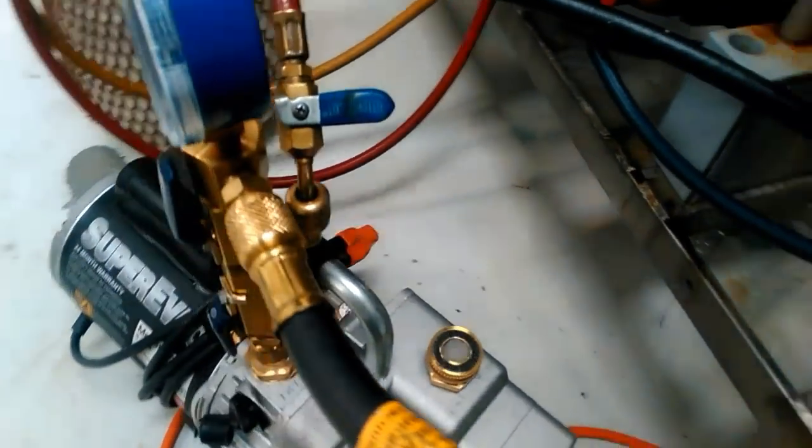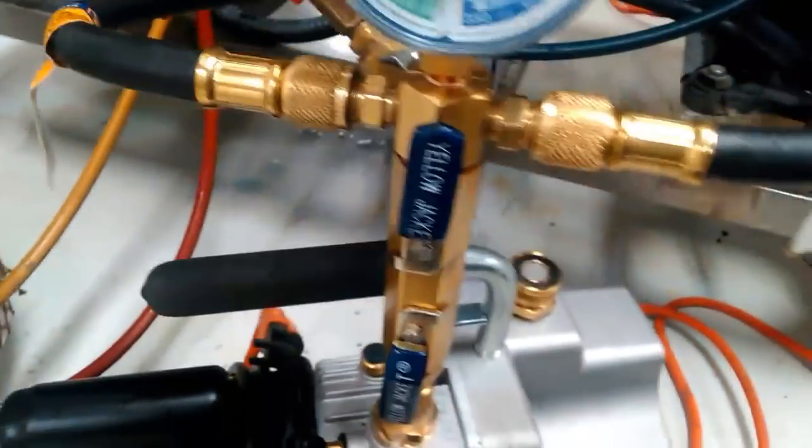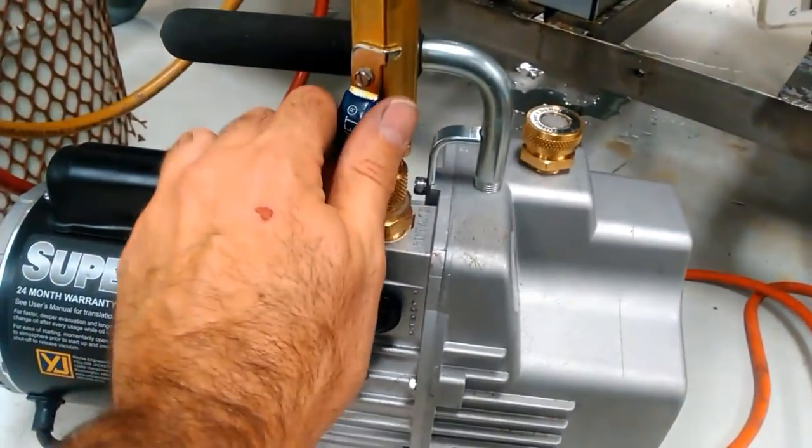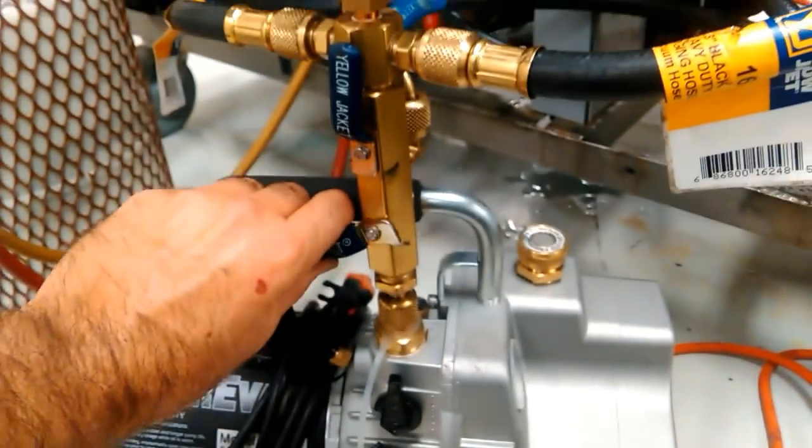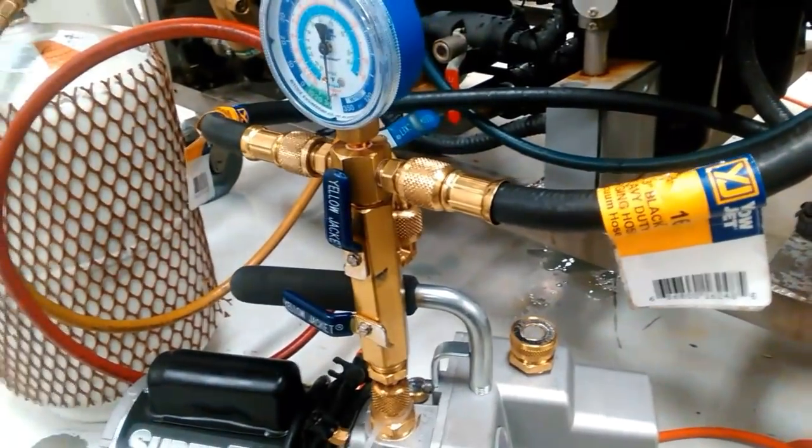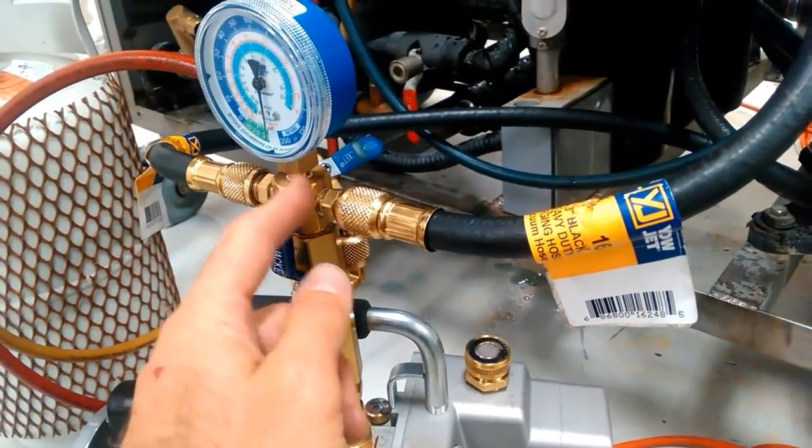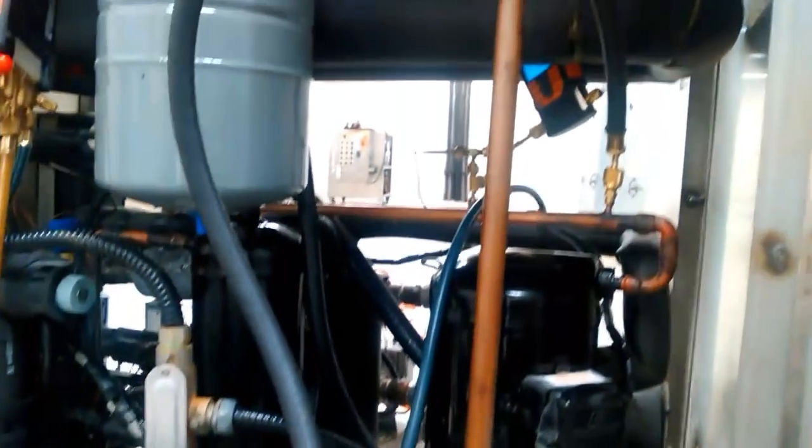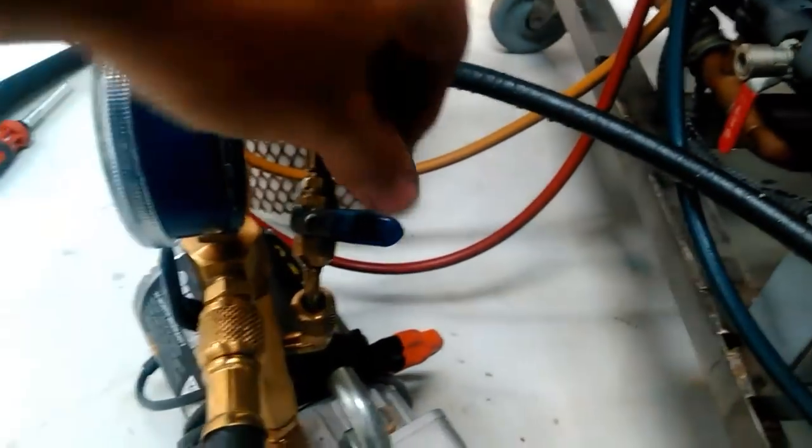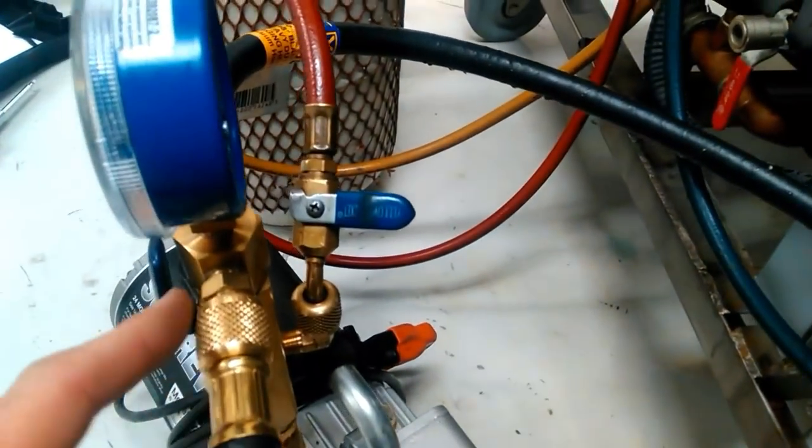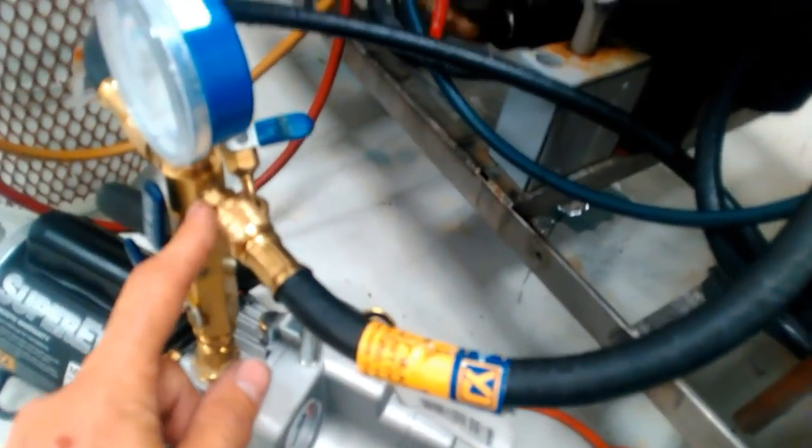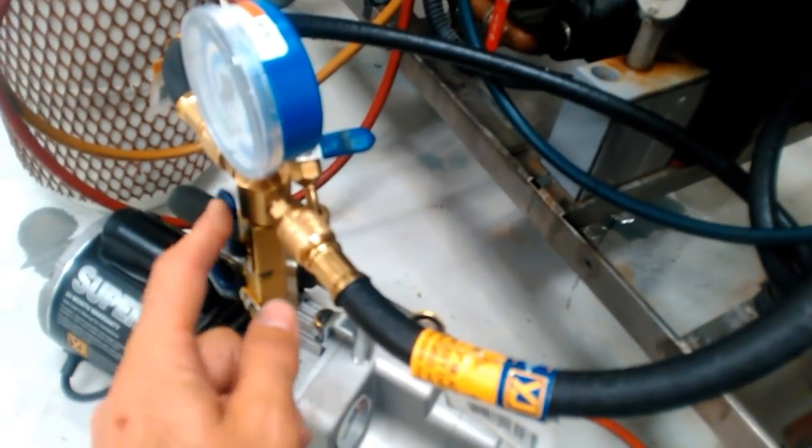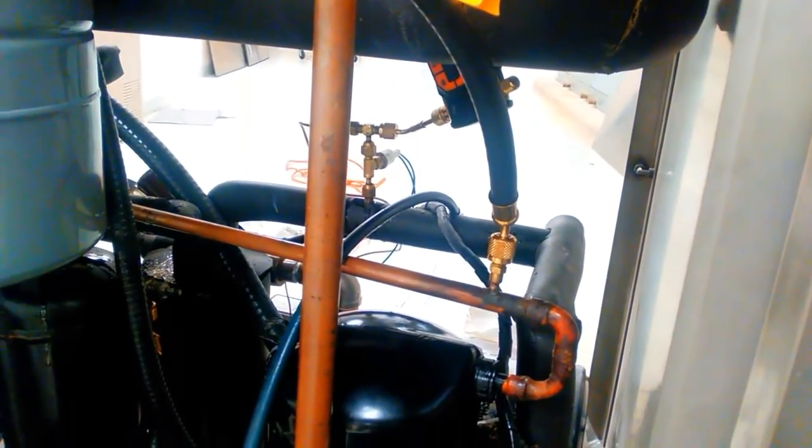Now when you're ready to put your holding charge in, it's very simple. You isolate the vacuum and now you're only open to the system. Now because you're open to the system, you can go ahead and open this ball valve up and your refrigerant will flow through the vacuum manifold, through the hoses, and into the system.